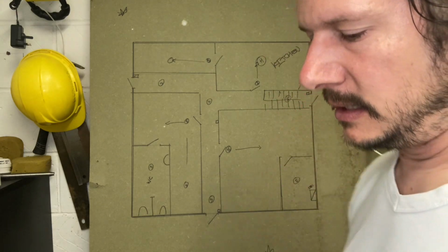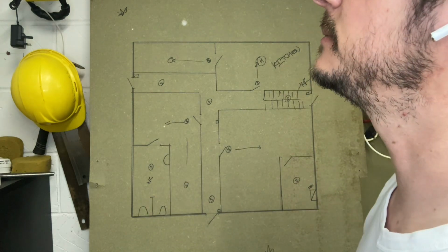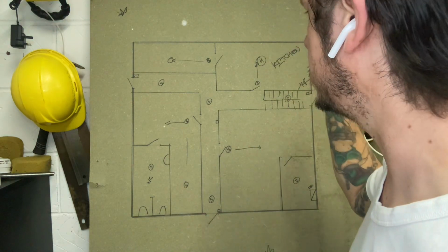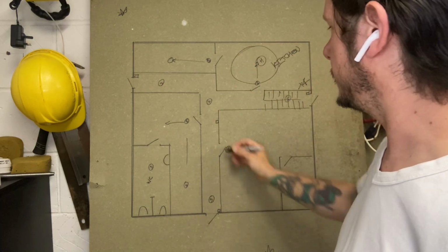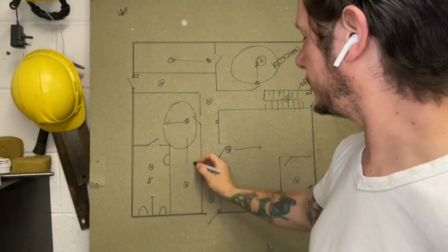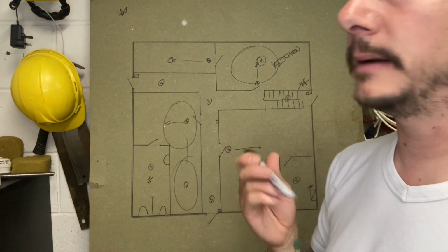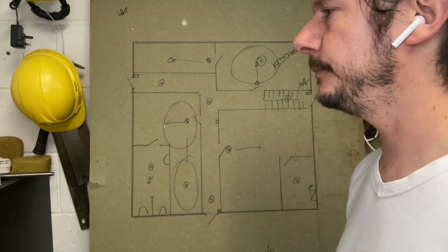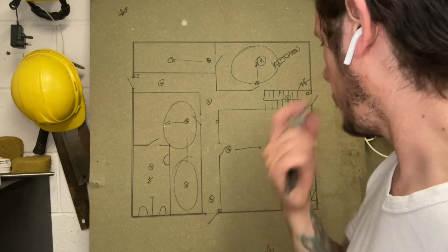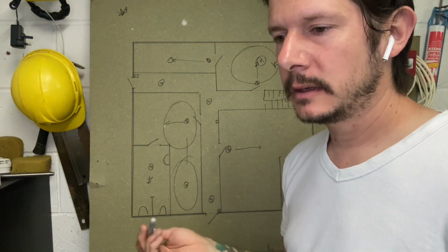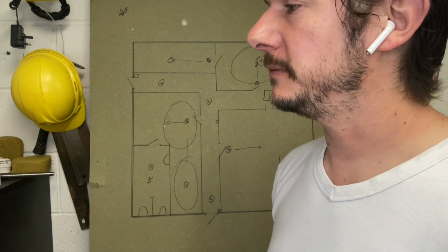Placement of devices. They need to circulate smoke detectors every, I always get this wrong, 7.5 meters, heat detectors every 5.3 meters. So you are talking about the area that it covers, which is why here I've gone, oh, there's an absence here, so I'm going to cover that area there, make sure we've got it. Again, that's going to be more into your L1 or your LDs generally. Cool. I think that covers it. Fire alarm engineers, fire engineers, by all means correct me in the comments. I think I've whipped through that quickly enough.